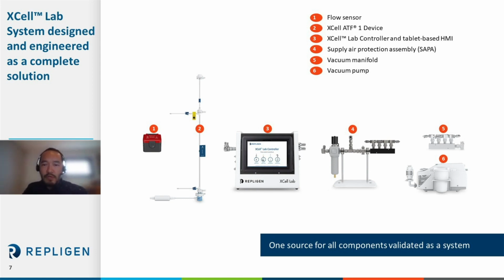The number two is, of course, our XCell ATF device. In this case, what's pictured is the new ATF1 format, and it can be equipped with integrated permeate pressure sensors, and I'll go through that a little bit later in the webinar. Number three is the XCell Lab controller. It's a controller itself, but it also has a tablet-based HMI, which can be attached magnetically to the controller, as you can see in the picture here, or it can be on a clamp stand. And part four here is what we call a SAPA, Supply Air Protection Assembly, which has all the parts necessary to properly condition the air utilities required for this new controller, such as down regulation of specific pressure.